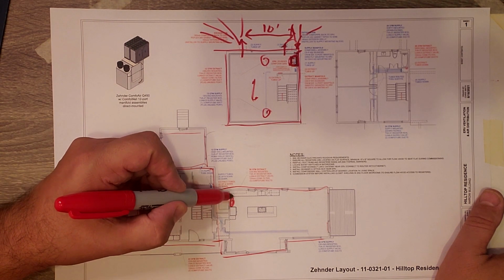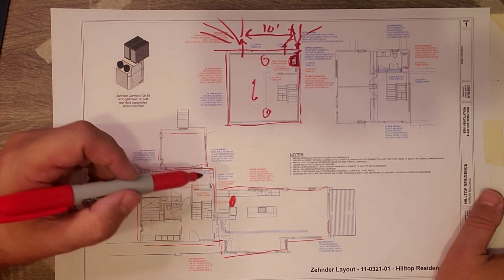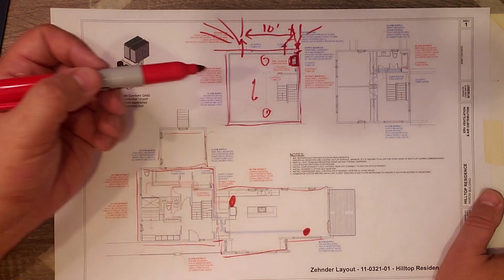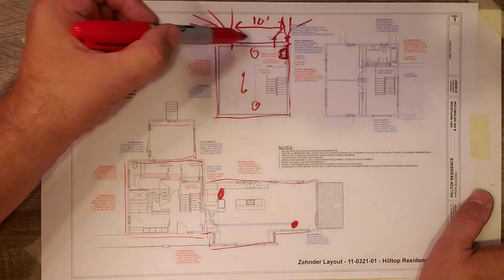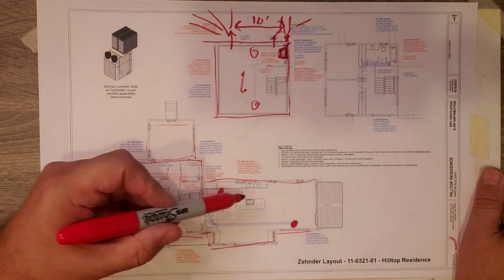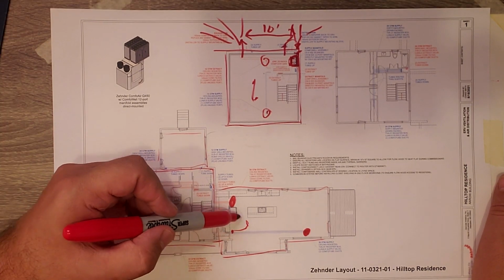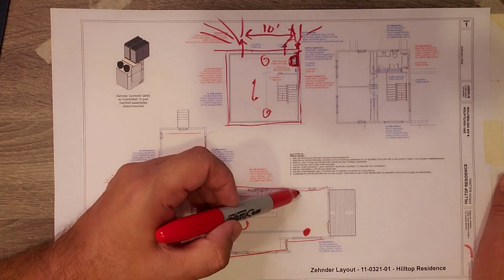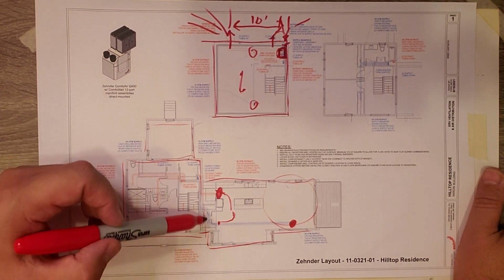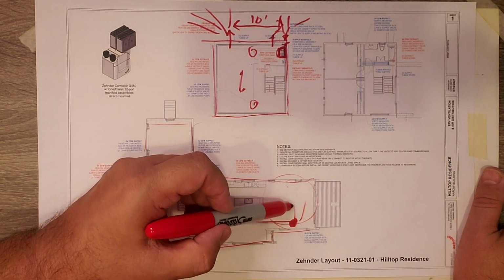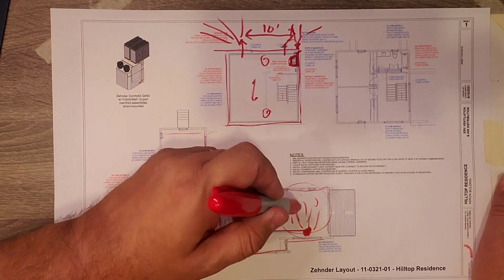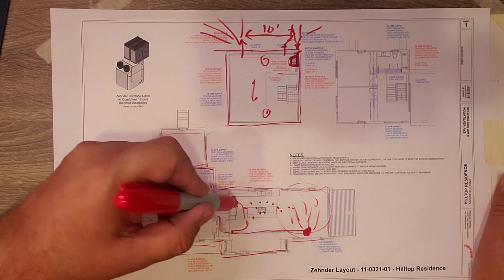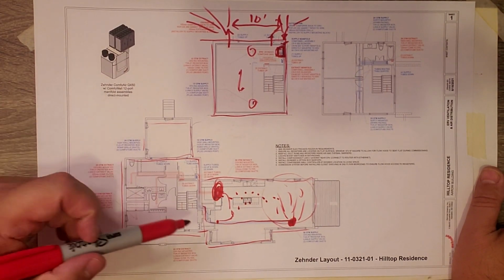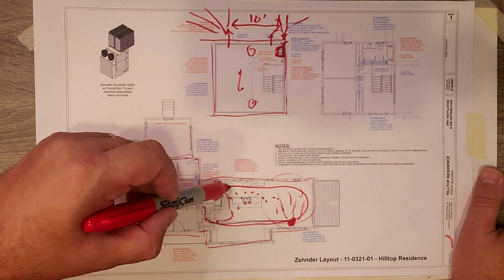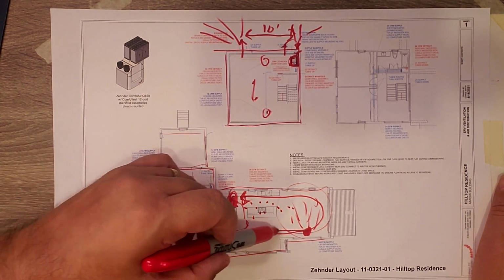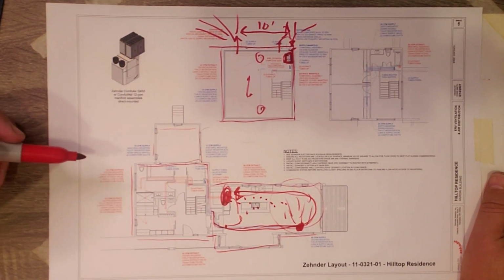We have some extraction area there, 36 CFM, and 36 CFM of supply. Just like we talked about with the 10-foot rule on the outside, you don't want these placed where the supply air gets sucked right back into the extraction without reaching the rest of the room. By bringing the supply deep into the room and distributing it there, the air slowly migrates toward the extraction point, creating a nice loop of outside air so the space gets fully ventilated.